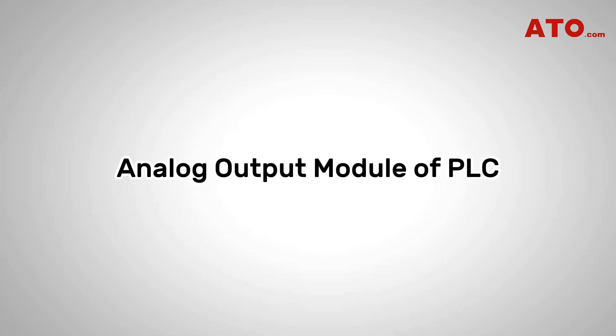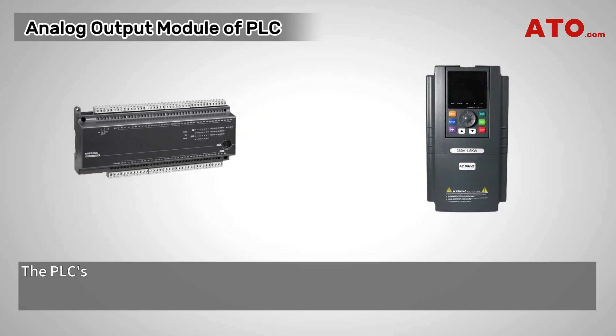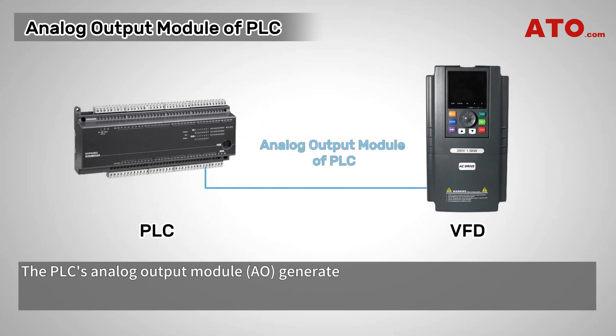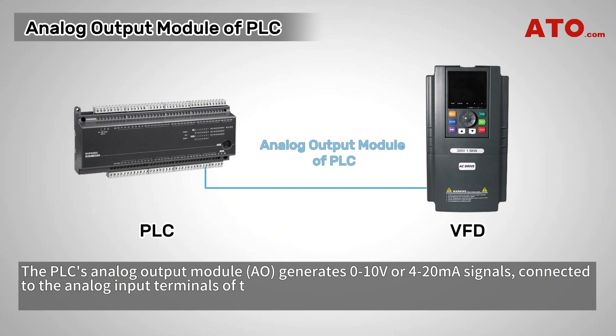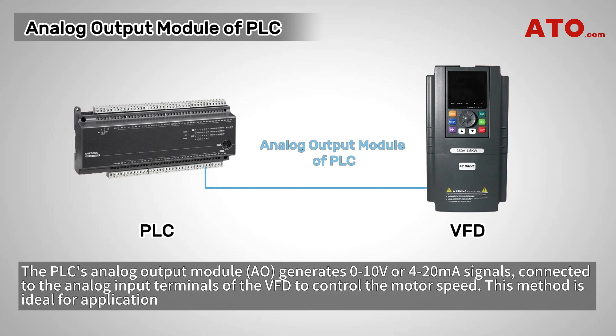The second method is the Analog Output Module of PLC. The PLC's analog output module generates 0-10 volt or 4-20 milliamp signals connected to the analog input terminals of the VFD to control the motor speed. This method is ideal for applications that require continuous speed adjustment.